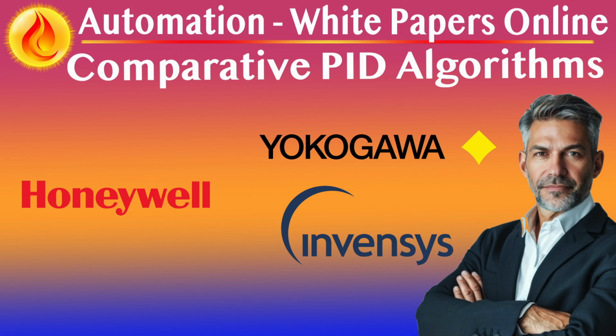In series algorithms, derivative interacts structurally with integral action, modifying effective gains. This causes reduced usable derivative range, increased sensitivity to tuning ratios, where D must often be less than I, and complex phase interactions that shift control dynamics. Filtering derivative with a time constant tied to D is essential to prevent overreaction to noise or spurious PV spikes.